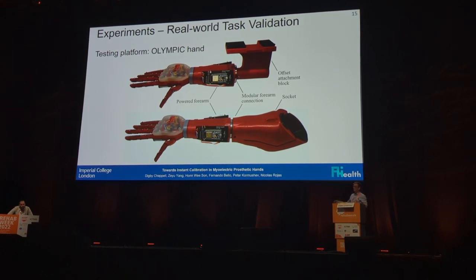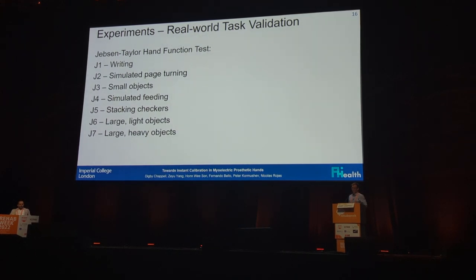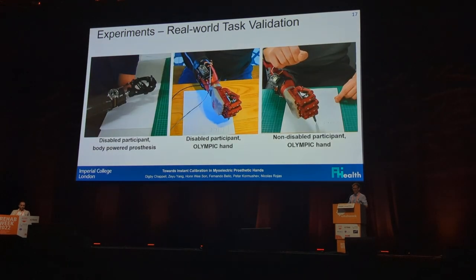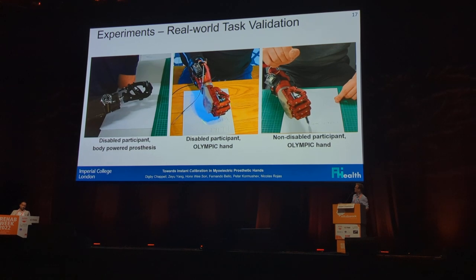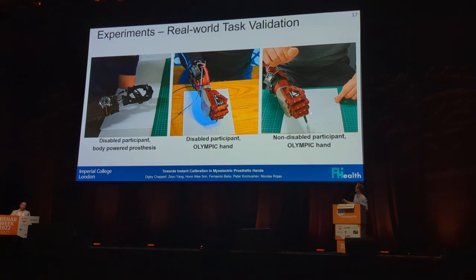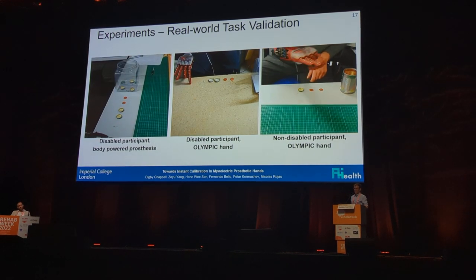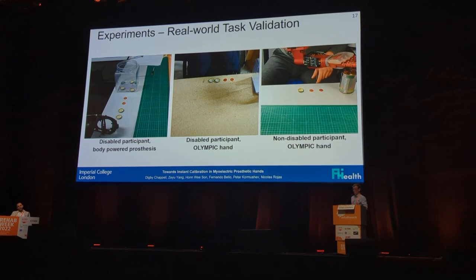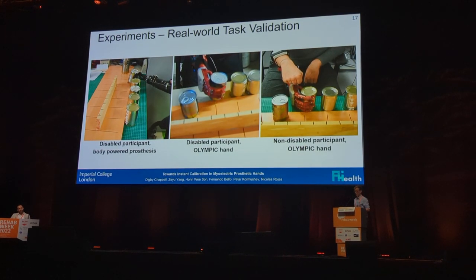So we used the Olympic hand — built by us in the lab — and tested it on the Jebsen-Taylor hand function test, which has a bunch of ADL-like tasks. We got the disabled participant to use their body power prosthesis and also the Olympic hand, and had 10 non-disabled participants using the Olympic hand. Tasks included picking up small objects — two paper clips, two bottle caps, and two pennies — and lifting large, heavy objects.